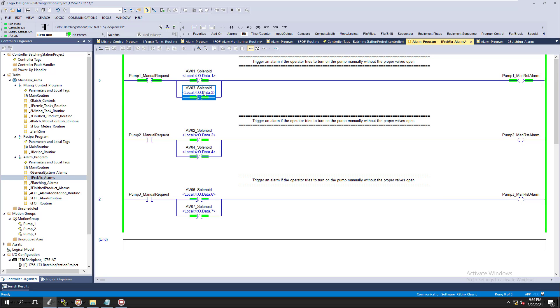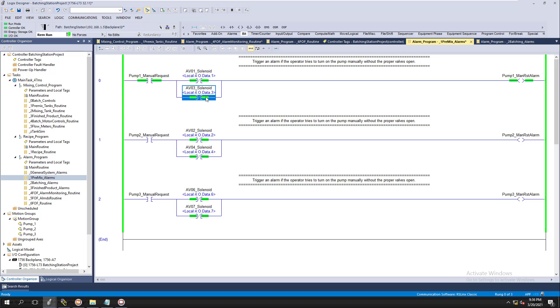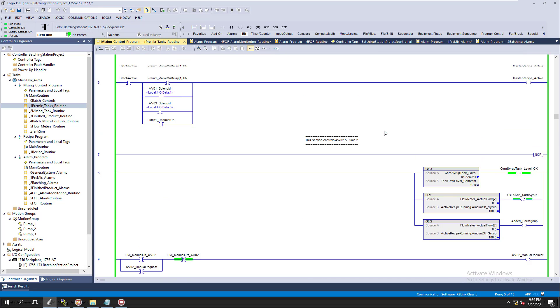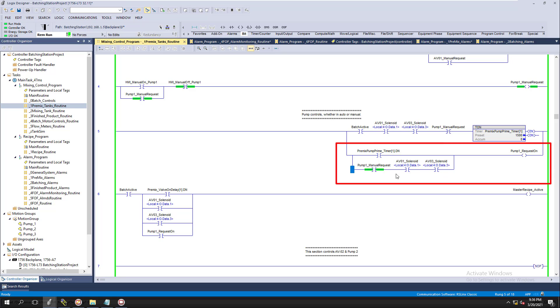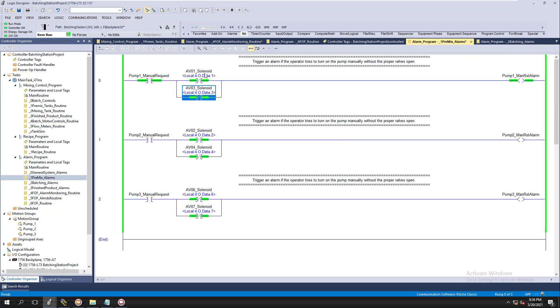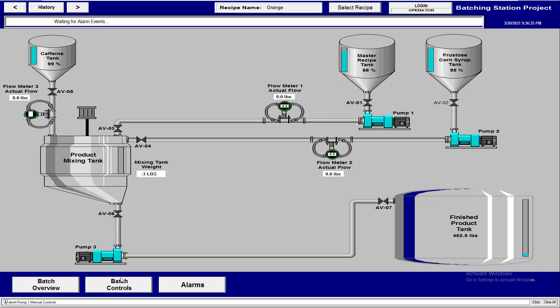Why are these in parallel instead of in series? Because if either one of these valves could potentially stop this from running, then either one of them could make this alarm happen. So we have to put this as an either/or condition — either one of these being missing will trigger the alarm.